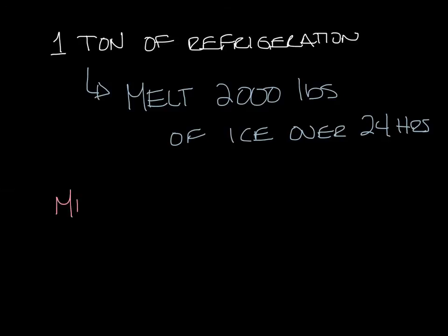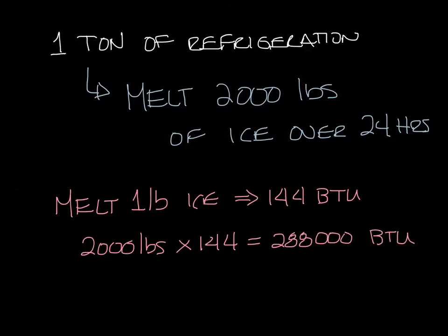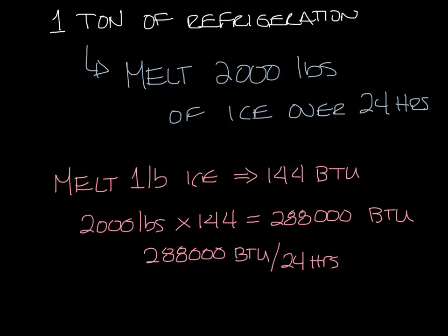When one pound of ice melts it absorbs 144 BTU. So for 2,000 pounds of ice, that would be 2,000 times 144, which equals 288,000 BTU. Now let's divide that by 24 hours, and you get 12,000 BTUs per hour — and that is equal to 1 ton of refrigeration.